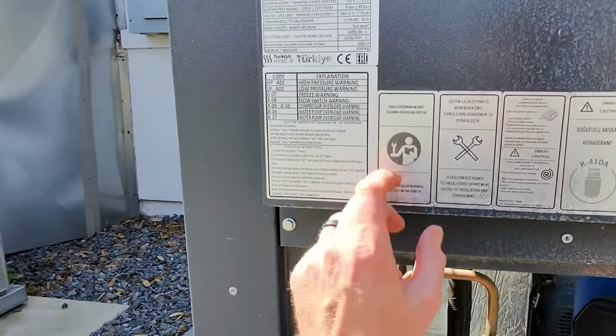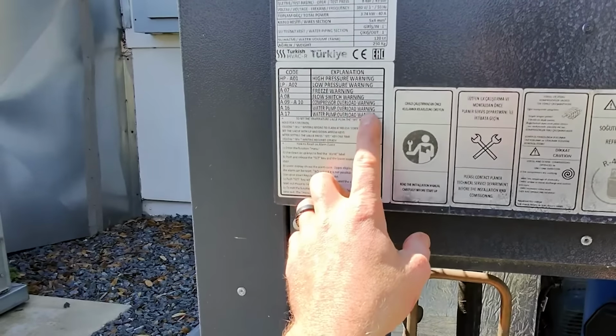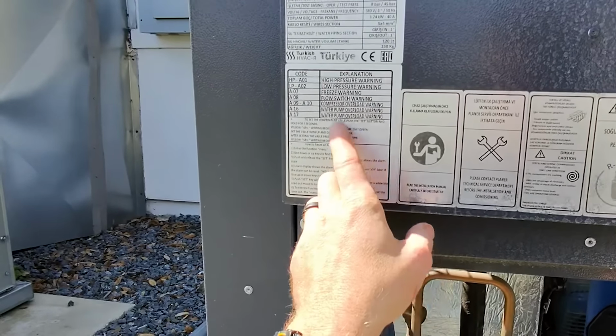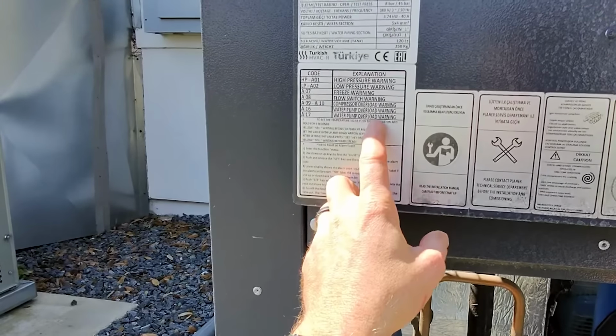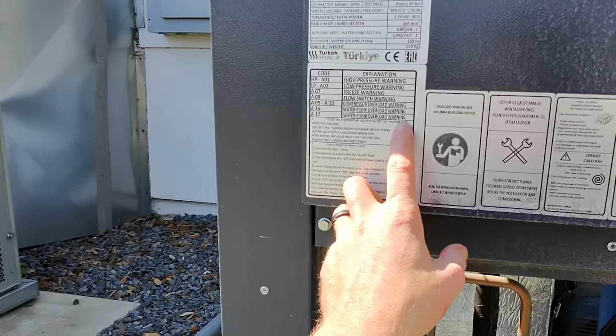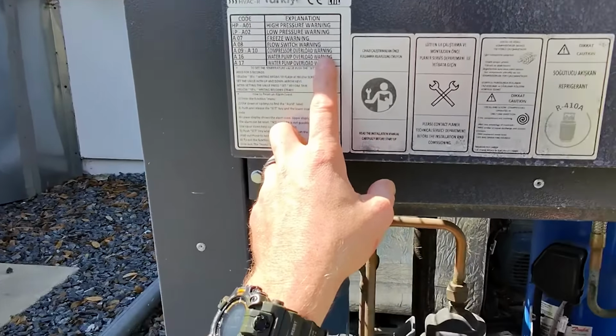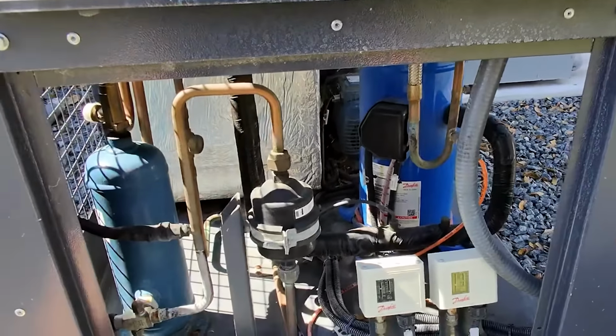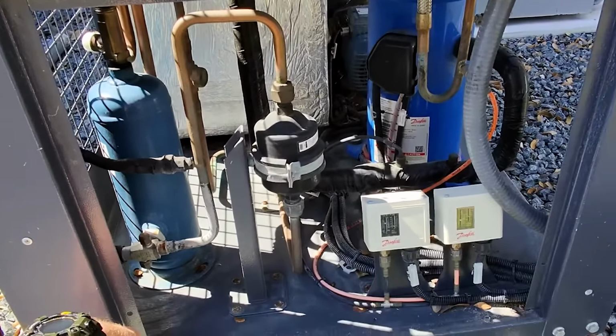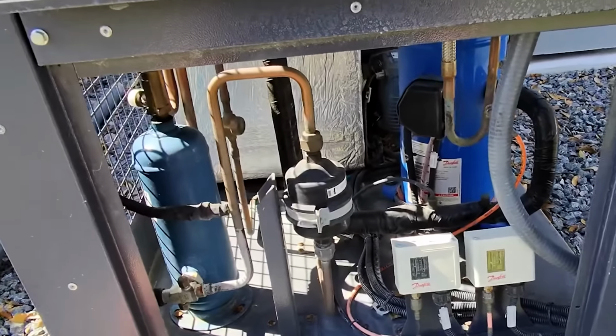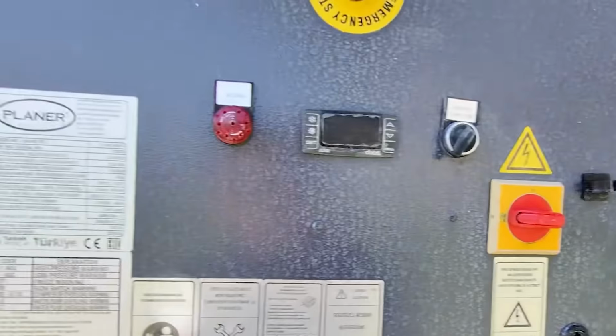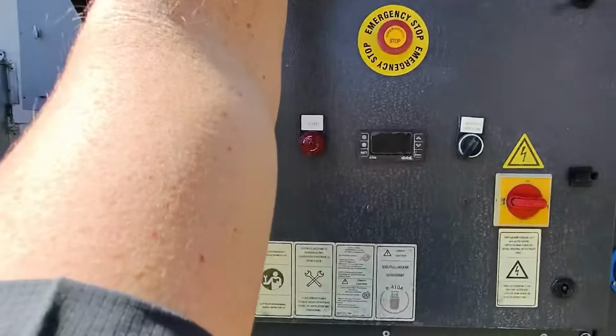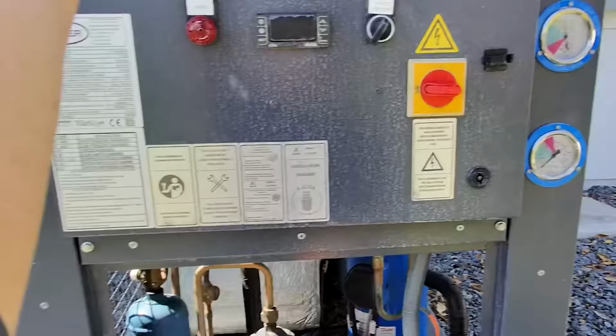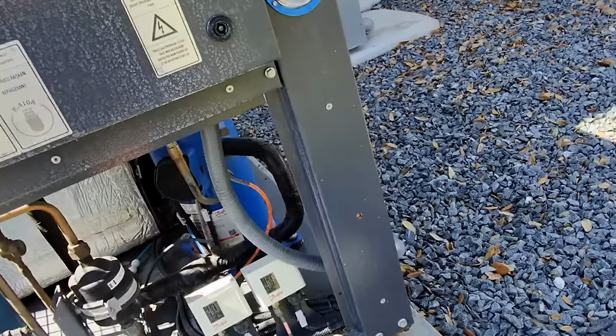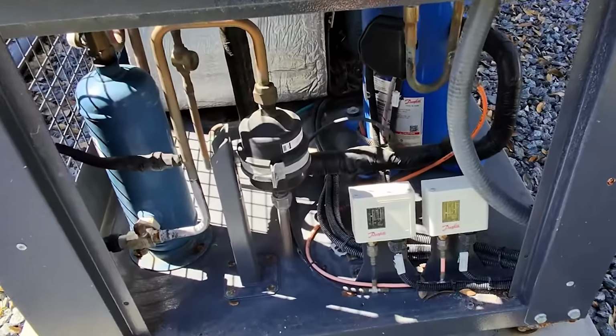It's saying it's kicking off because of water pump overload warning, but also it's on there twice, water pump overload warning. So you've got two different water pump overload warnings. And there's a compressor overload warning, which we're not getting, but it is turning off that Danfoss compressor a while after. So it doesn't make a lot of sense. So let's go get some tools. Let's gauge up before we call the boys in Germany to ask them what the heck we're looking at here. And yeah, it's a pretty interesting piece of equipment.